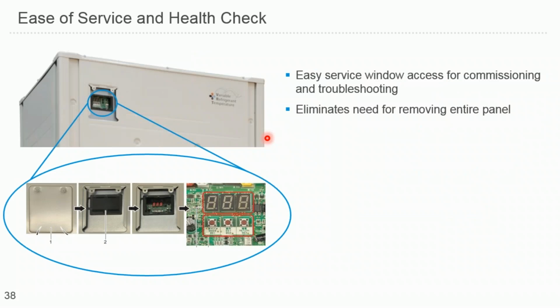Let's look at the servicing and commissioning. The service window, as I mentioned earlier, will be a new addition. You don't need to take out the whole panel now to have access to these digital indicators you see over here. All you have to do is take out these two screws and open that window, and you're good to go, and you can make your field setting changes there.